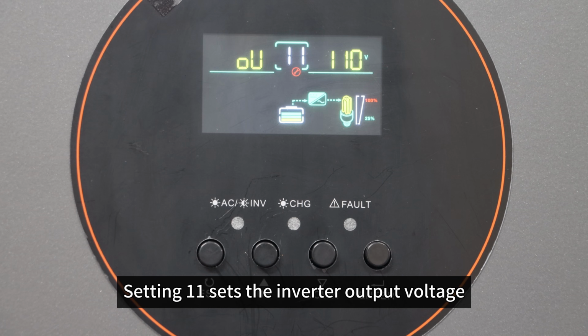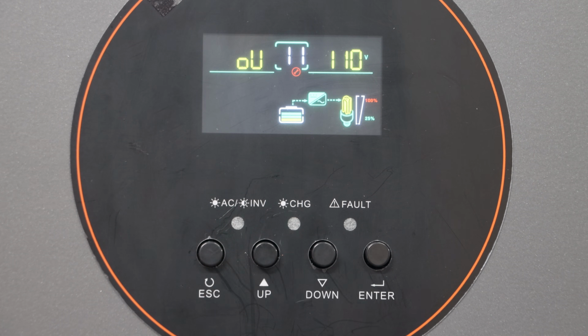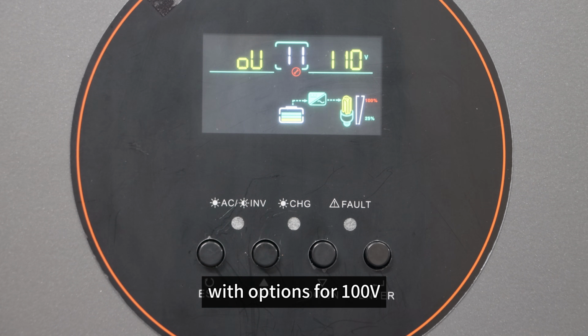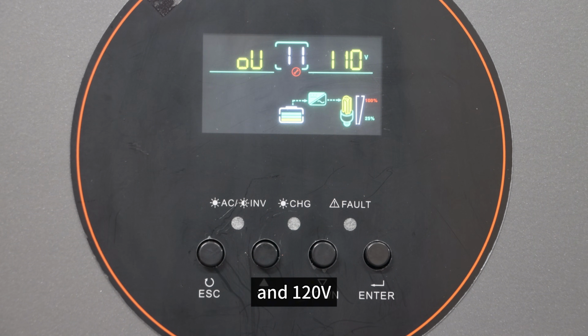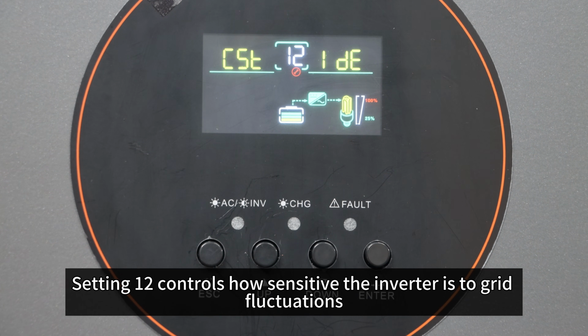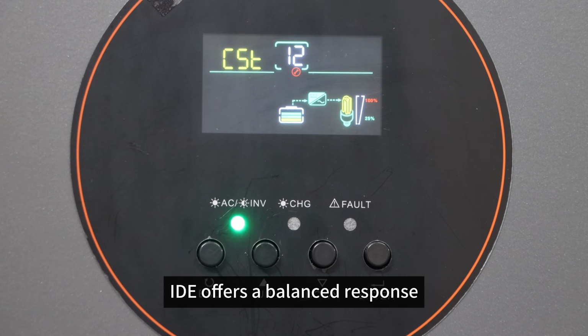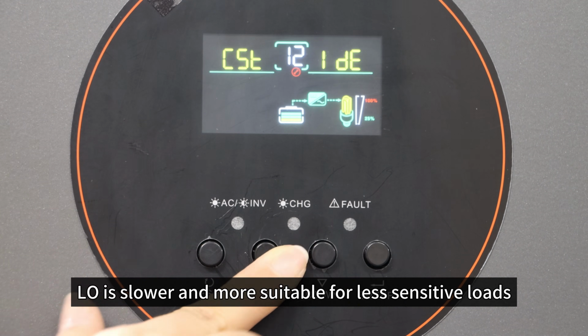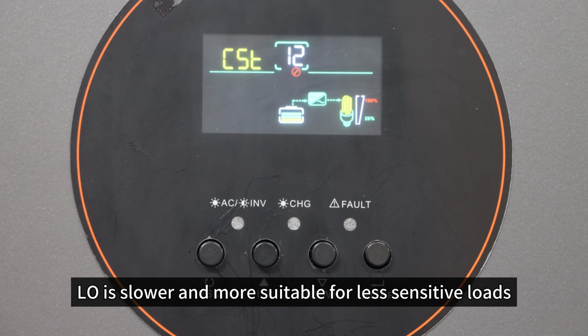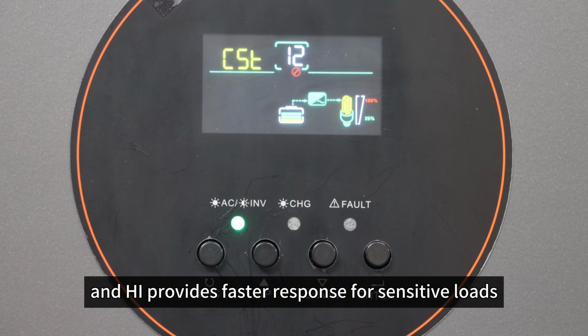Setting 11 sets inverter output voltage with options for 100 volts, 110 volts, and 120 volts. Setting 12 controls how sensitive the inverter is to grid fluctuations. IDE offers a balanced response. LO is slower and more suitable for less sensitive loads, and HI provides faster response for sensitive loads.